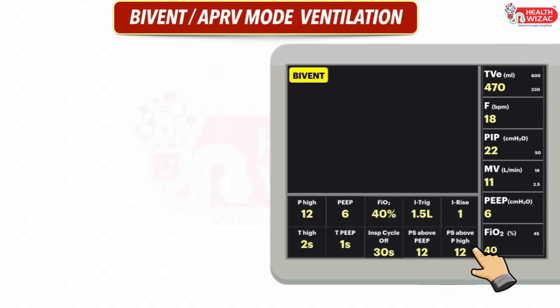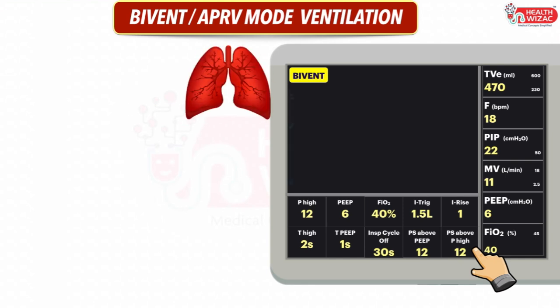Next is Bi-Vent mode, also referred to as APRV mode (Airway Pressure Release Ventilation) in some machines. In this mode we have to set P-high, T-high, PEEP, T-PEEP, FiO2, inspiratory cycle off time, inspiratory trigger, PS above PEEP, inspiratory rise time, and PS above P-high.